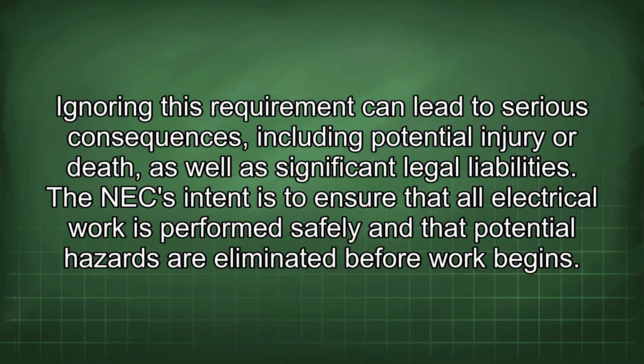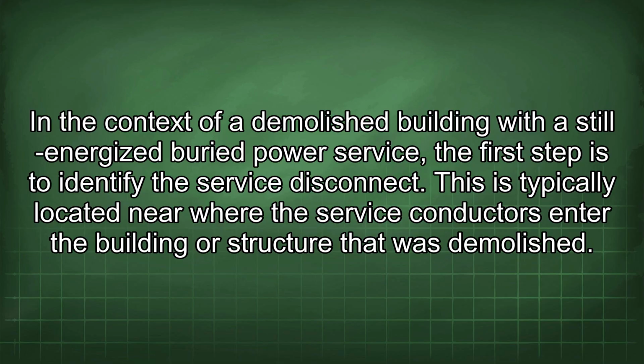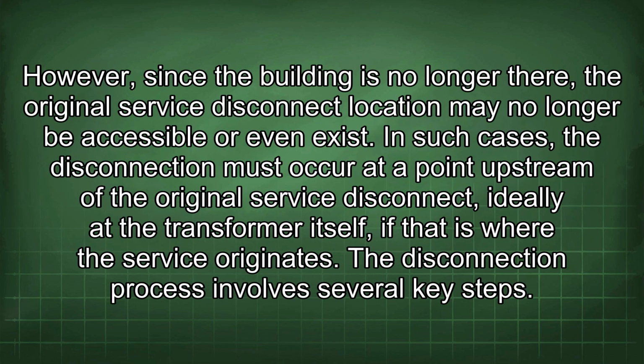Ignoring this requirement can lead to serious consequences, including potential injury or death, as well as significant legal liabilities. The NEC intent is to ensure that all electrical work is performed safely and that potential hazards are eliminated before work begins. In the context of a demolished building with a still energized buried power service, the first step is to identify the service disconnect. This is typically located near where the service conductors enter the building or structure that was demolished. However, since the building is no longer there, the original service disconnect location may no longer be accessible or even exist. In such cases, the disconnection must occur at a point upstream of the original service disconnect, ideally at the transformer itself, if that is where the service originates.